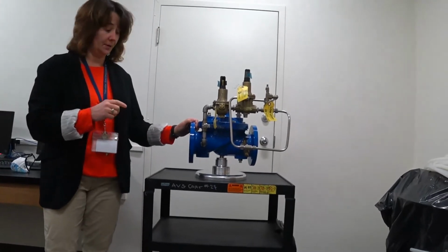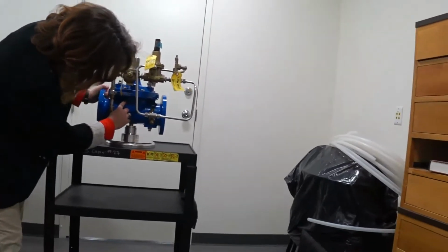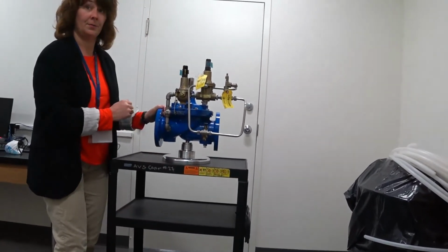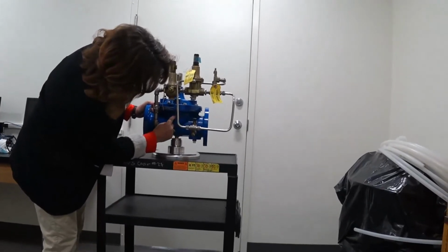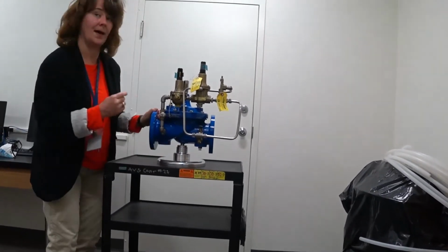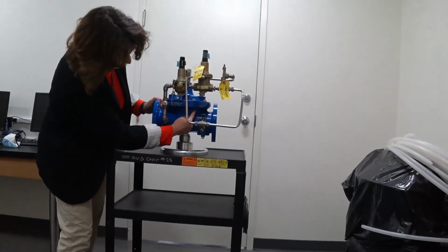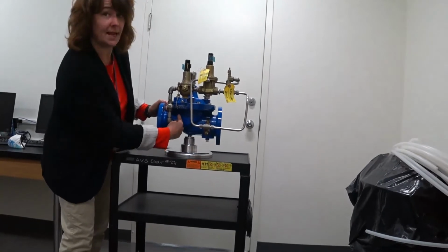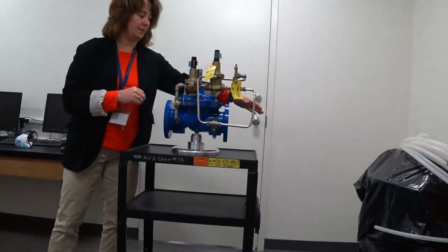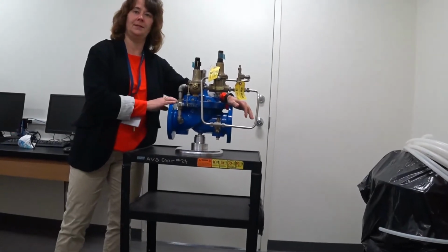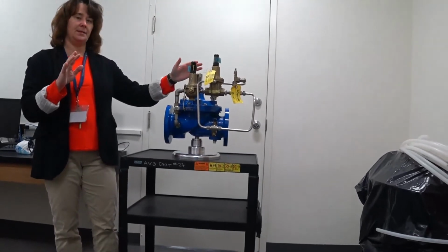the water's flowing. So I always come and look at the outside of the valve, and I look at the line on the back. You'll notice it's got an upside here, and then the line comes across, and then it goes down on that side, in the casting. So this is the upstream side, this is the downstream side. As soon as I have that, I know that this is high pressure and this is low pressure.